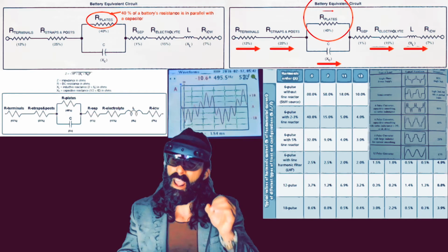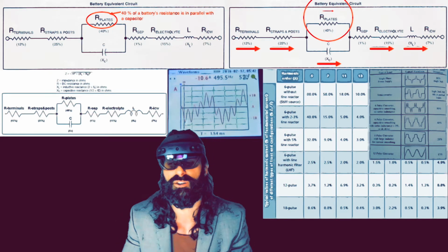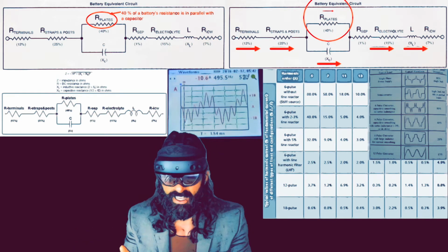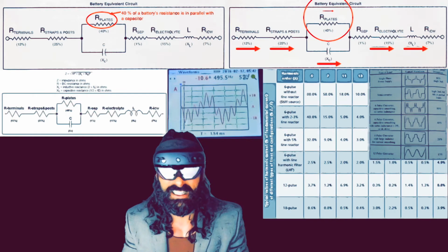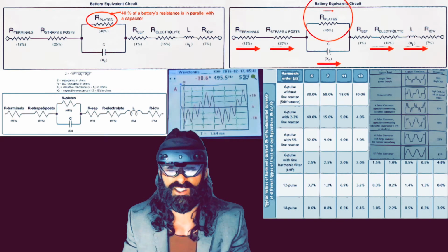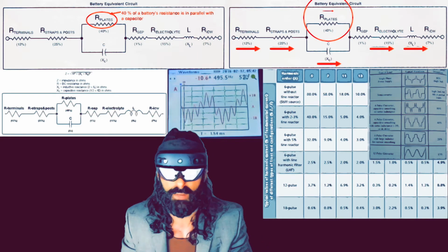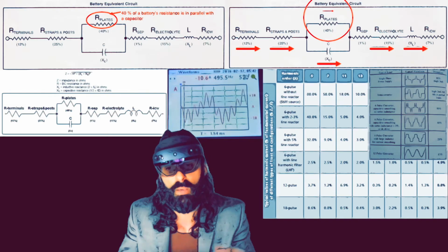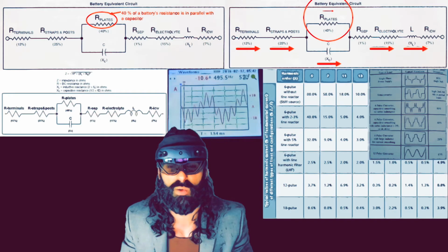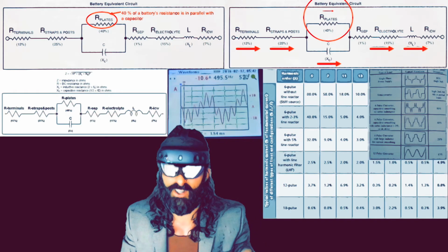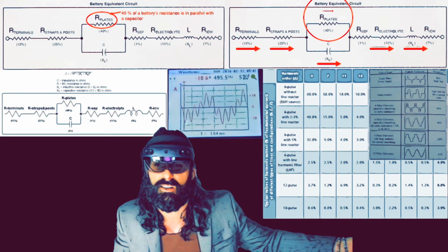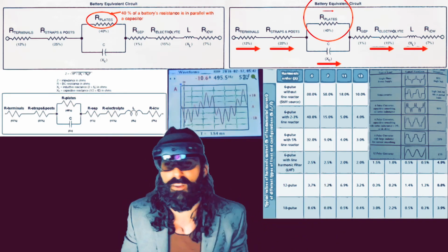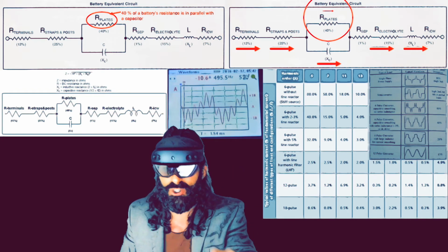It'll be gone. And I review these things in detail because in the data center industry, these terms get interchanged and exchanged commonly, daily. Every time I go to a site, someone is projecting to me that impedance and conductance is the same as resistance, because on their terminology, on their marketing material, I call it fluff, they put resistance values because they want to trick you. They want you to think that resistance resolution, which is usually AC conductance or impedance, is the same as a DC resistance methodology, where that's 6 millionths of an ohm, 6 decimal places on the resolution. These systems do not have that kind of resolution, not at all.